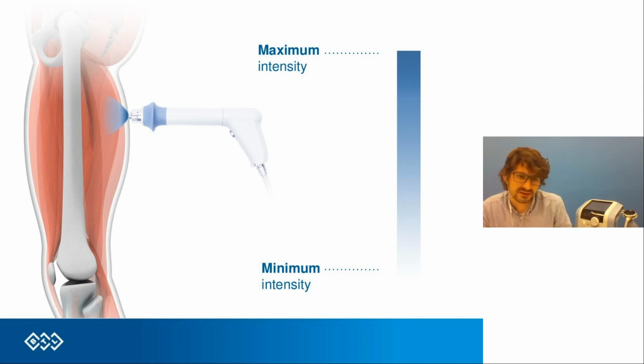Okay, so with the distance, that's a perfect example. If you have some calcification that is, let's say, deep inside of the patient's body, you are not able to affect it with enough strength, enough intensity, because the problem is that you will have to use the maximum intensity, and you will have this maximum intensity superficially. So you will be affecting the skin and the muscles with very strong perception, very strong shocks, but at the same time, you will not be affecting the calcification with the intensity that you need.